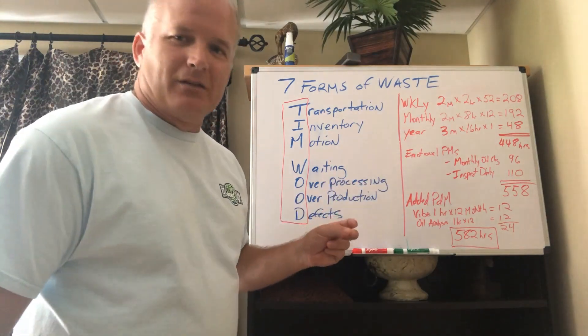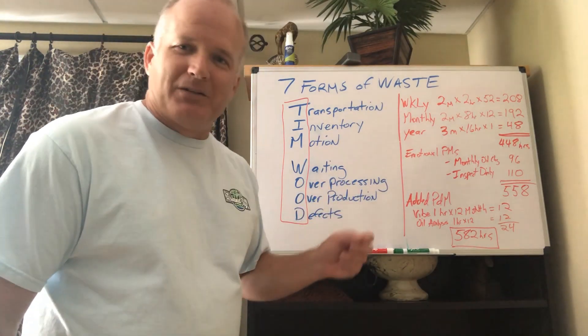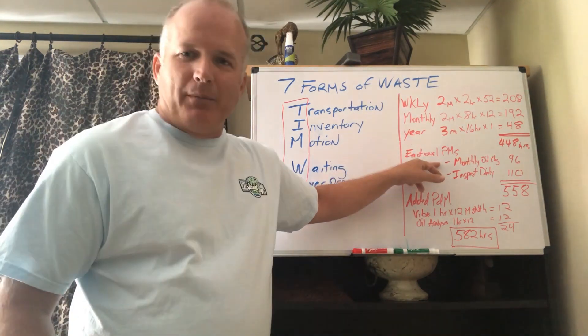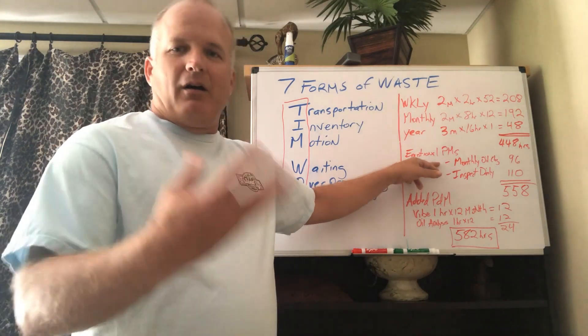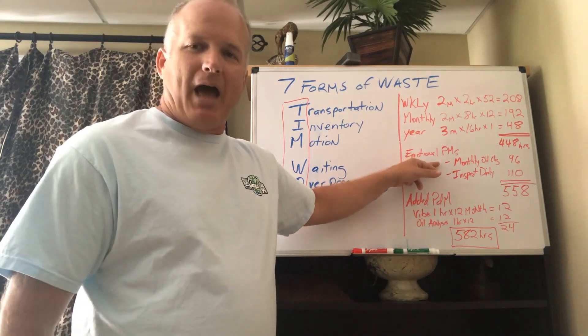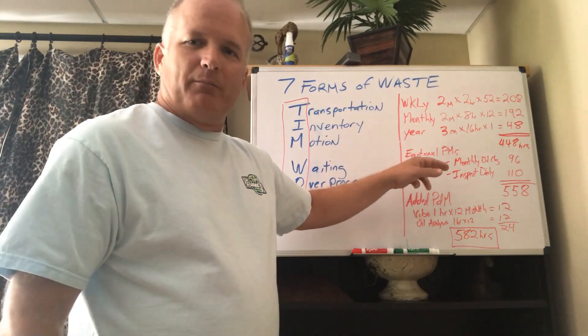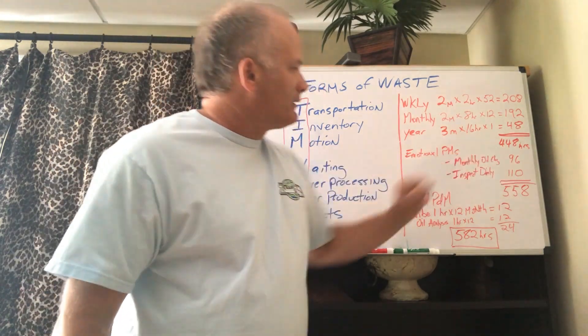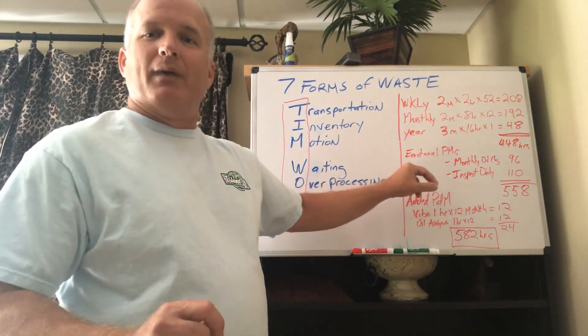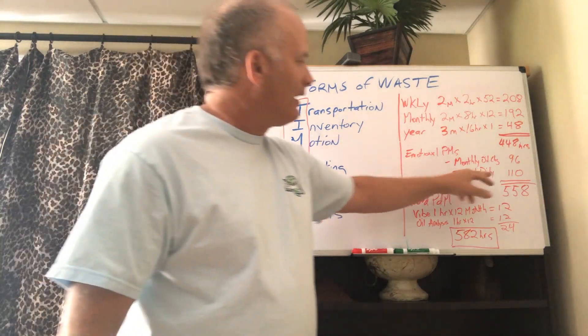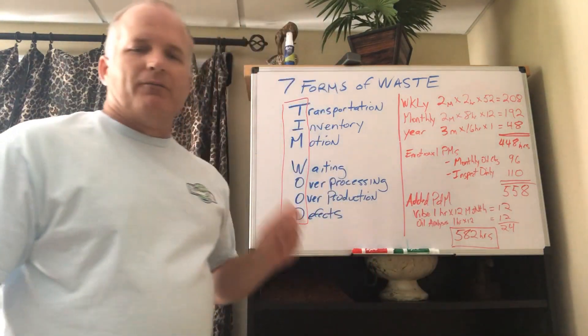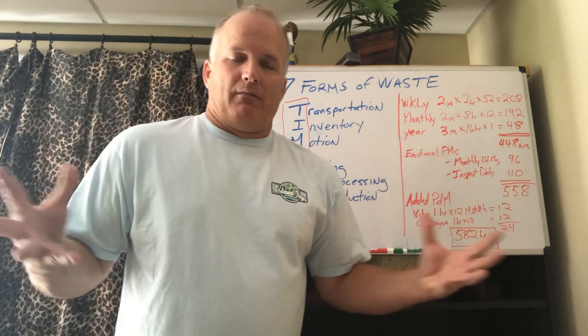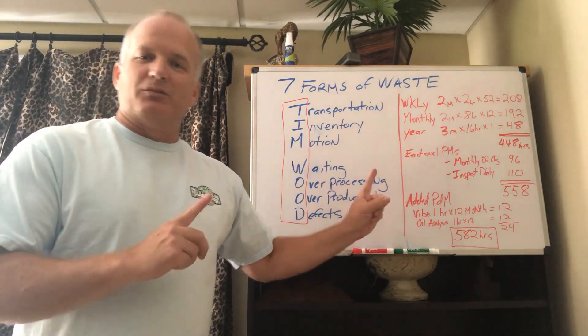Now here's the key — we had some emotional PMs. What are emotional PMs? These are PMs done out of fear, not based on failure mode. We had an event happen and the reaction of the organization was 'we don't want that to happen again.' So regardless of whether it was based on failure mode, we decided to change the oil every single month — 96 hours — and inspect daily: 20 minutes for one person daily, that's 110 hours. Total investment: 558 hours a year into maintaining that asset.